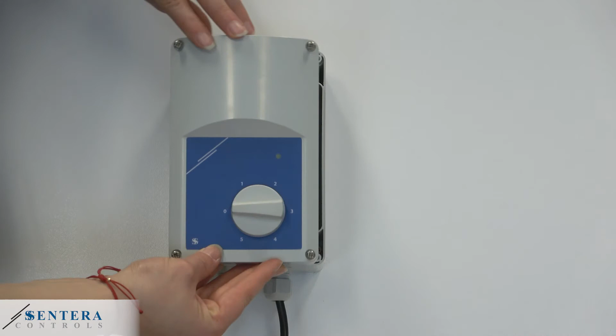The STR1 series have a maximum current between 0.8 to 7.5 amperes depending on the version. One or multiple identical motors can be connected to this controller as long as their combined maximum current does not exceed the maximum current rating of the fan speed controller. There is no need to overdimension the fan speed controller.